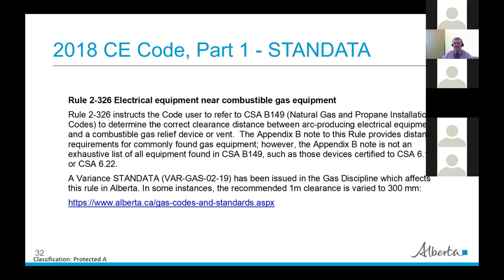Another STANDATA for Part 1 recognizes what's going on in the gas discipline. Rule 2-326 refers to CSA B149, the Natural Gas and Propane Installation Code. There's been a variance issued under the gas discipline which affects that rule in Alberta — in some instances the recommended one-metre clearance is varied to 300 millimetres. We make reference to CSA B149 but also let people know there's a variance on that, so check with your gas SCO.